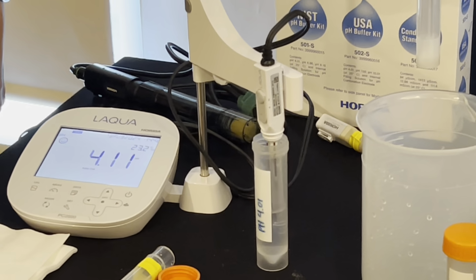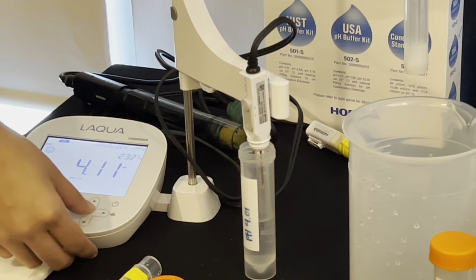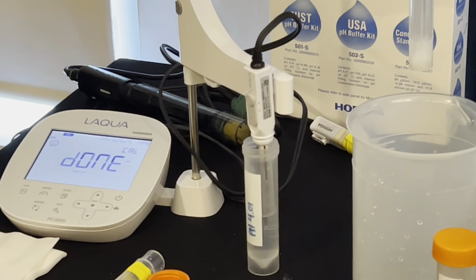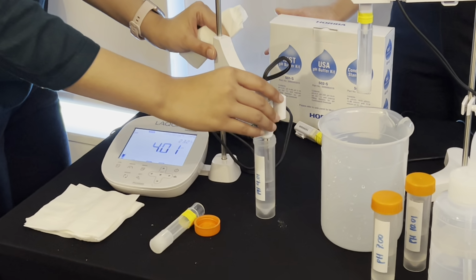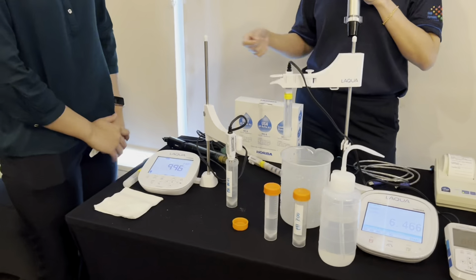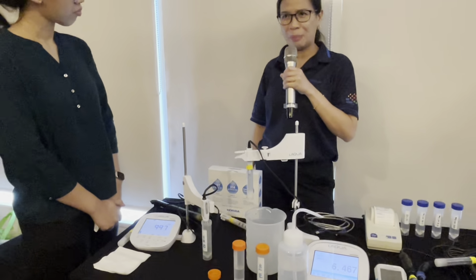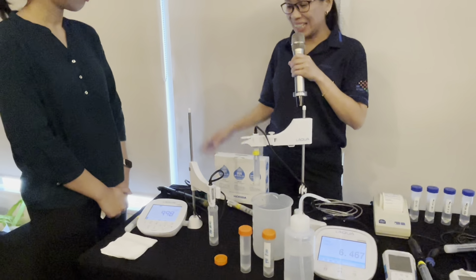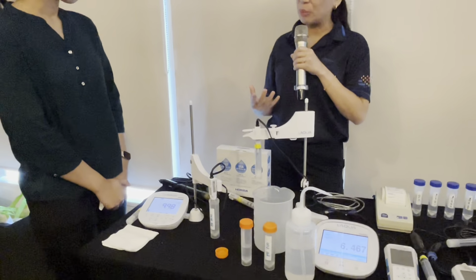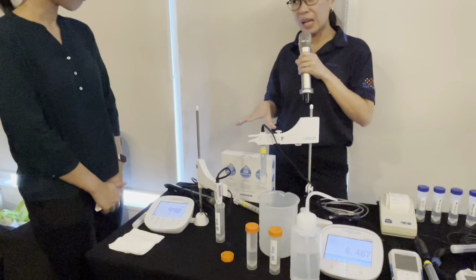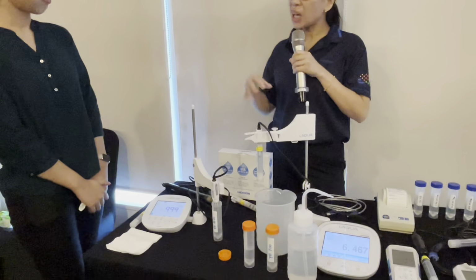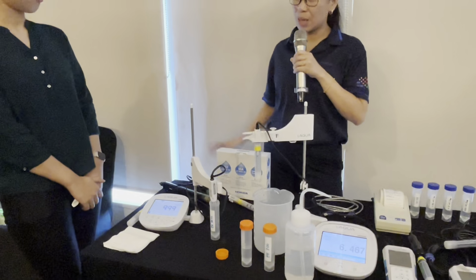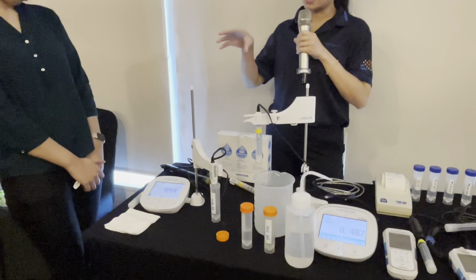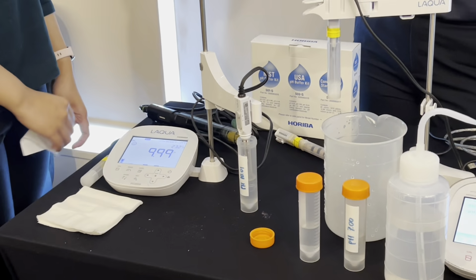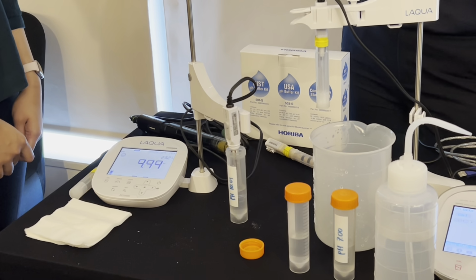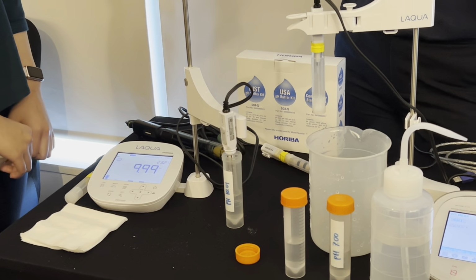Okay, it says it's stable, so we can press the enter button. Okay, so now it says cal done, right? So the reading is 4.01 after. Like when they immerse, then they press cal immediately, right? But then you see the reading is still not stable. Because if you press the cal button immediately, it will calibrate a not-yet-stable reading. Sometimes it's stable, but then it changes again, the smiley disappears because it's not yet fully stable. We have to wait for the reading to stabilize.